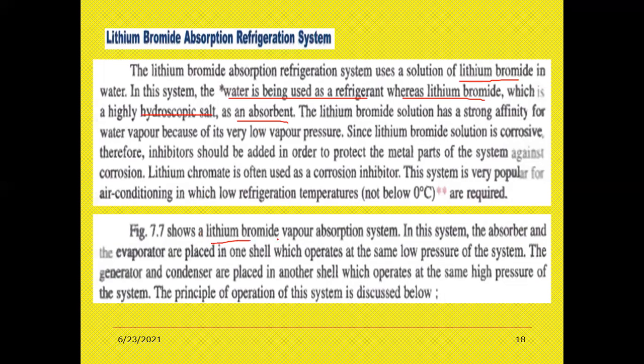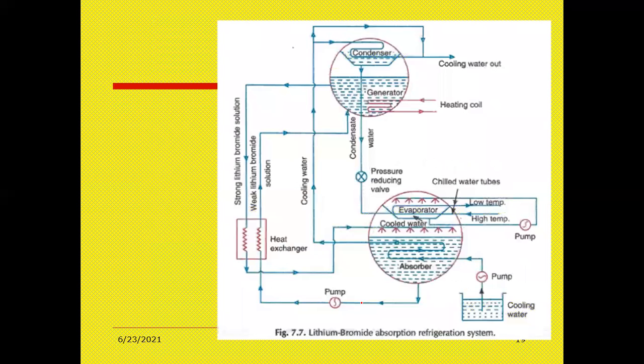Here, a figure shows the lithium bromide vapor absorption system. In this system, the absorber and the evaporator are placed in a shell which operates at the same low pressure of the system. The generator and the condenser are placed in another shell which operates at the same high pressure of the system. The principle of operation of this system is discussed now. See the figure of the lithium bromide absorption refrigeration system. Here we are having an evaporator, here we are having a condenser and a generator. Here we are having a heat exchanger, and here we are having cooling water. So that is a simple setup of the lithium bromide absorption refrigeration system.